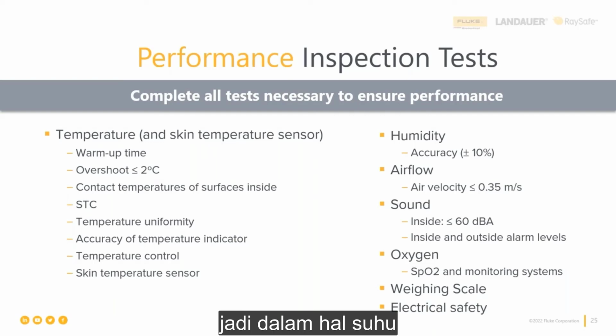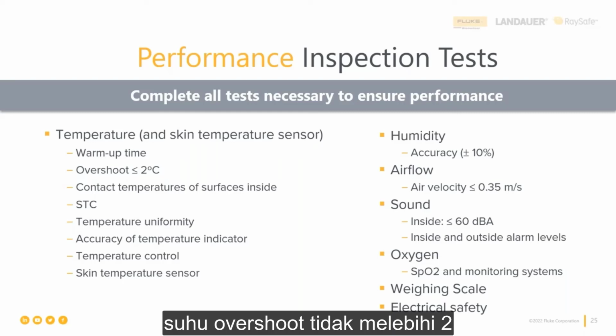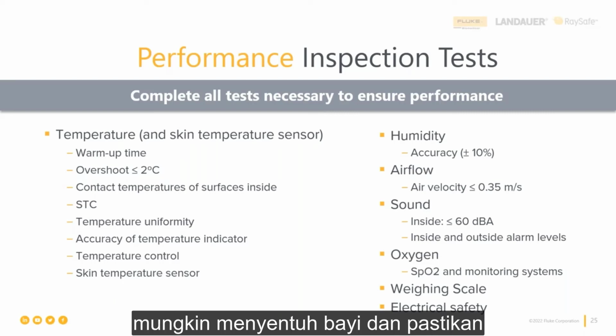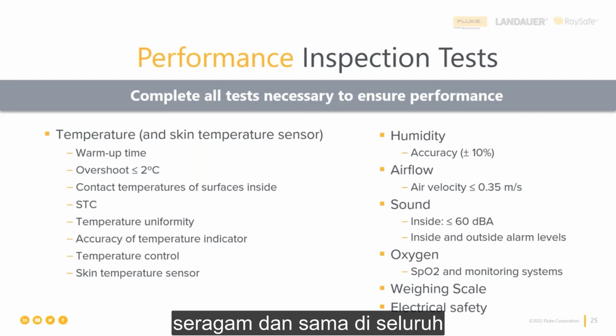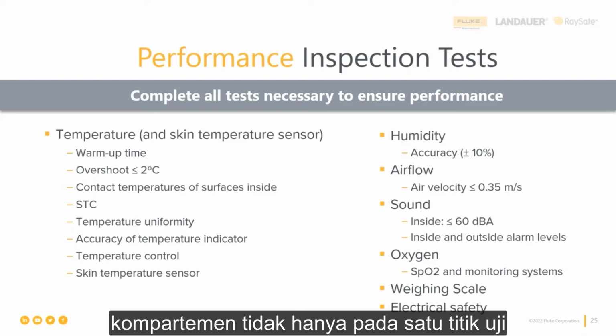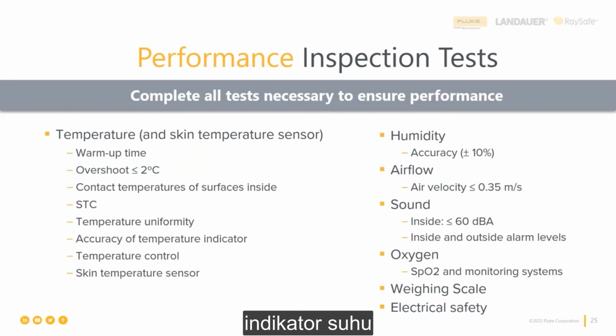So in terms of temperature, you want to make sure that your incubator warms up in the time specified in the manufacturer's manual. You want to test to ensure that the overshoot temperature doesn't exceed 2 degrees Celsius of the set point. You want to check all surfaces that might touch the infant and make sure that they do not get too hot. You want to test to determine when the incubator's temperature stabilizes and stays at that temperature setting for at least an hour, right? So there's your STC. You want to verify the temperature is uniform and the same throughout the compartment, not just at one test point. You want to check the accuracy of the temperature indicator itself. And you want to make sure that the temperature control sets the temperature to the correct value.